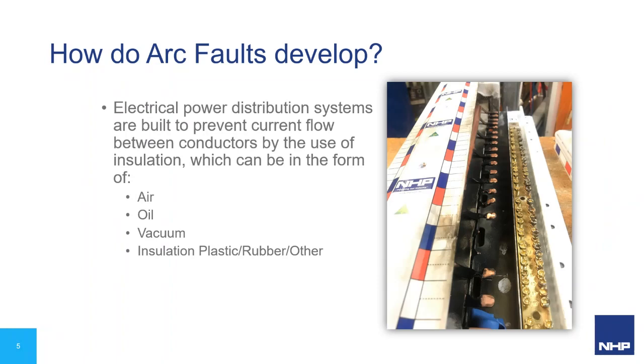So how do arc faults develop? Electrical power distribution systems are used to prevent current flow between conductors by the use of insulation. Air, oil, vacuum, plastic, rubber, all sorts of things can be used for that. But effectively what we're trying to do is get power down the conductors and not between them. On the right hand side here, we've got a miniature circuit breaker chassis. This one actually experienced an arc fault event, and I will go into a little bit more detail on that in a minute. But you can see there that an air gap is used as you go between those tags to separate out those conductors.